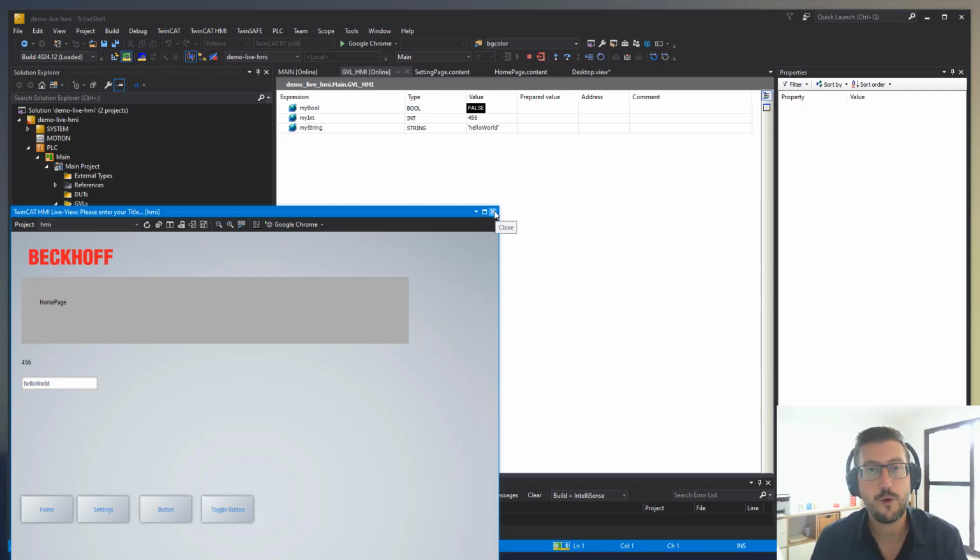And have an explore through. We've got gauges, we've got sliders, all sorts of things. Again, some of the sliders, you may need to double click on them and say they're a two-way binding, because the sliders will update themselves. But if you tick editable and then slide it backwards and forwards, it may not write the value back to the PLC. It will hold it in the front, but it won't write it to the back. So just make sure that you're aware of that.